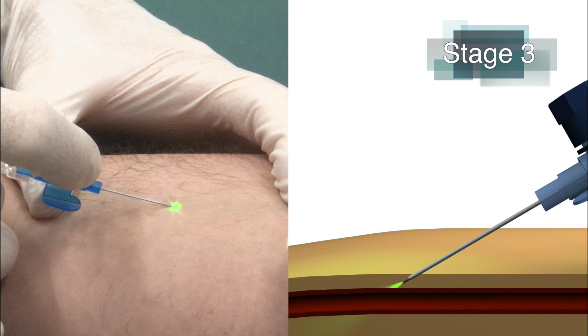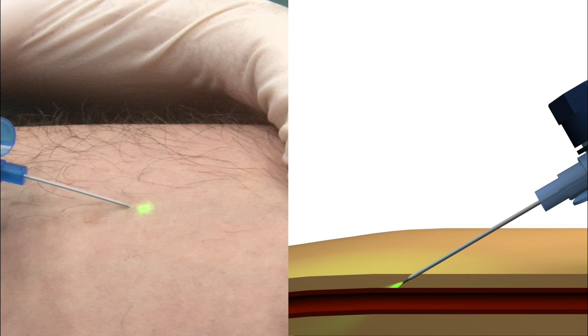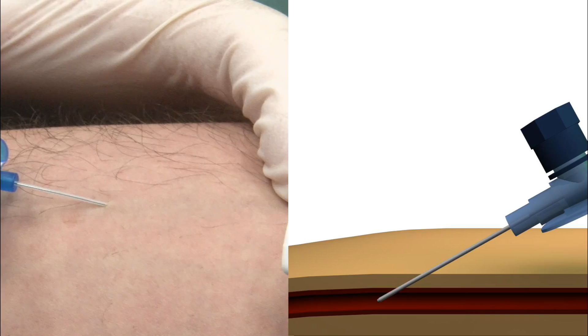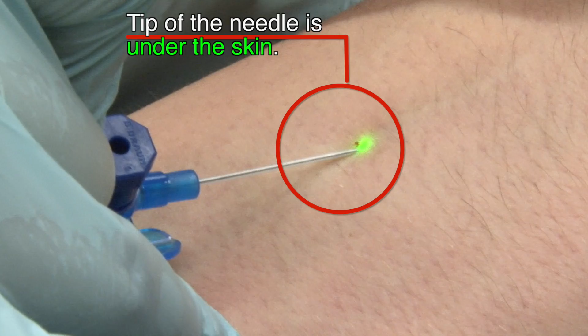Penetrate the skin at an angle of 15 to 30 degrees and advance the tip of the catheter toward the target vessel. Observe the instant disappearance of the green light at the tip of the catheter, which is a sign of penetration of the wall of the vessel. Green light will be visible also through dark skin, but higher brightness of the laser light might be required.